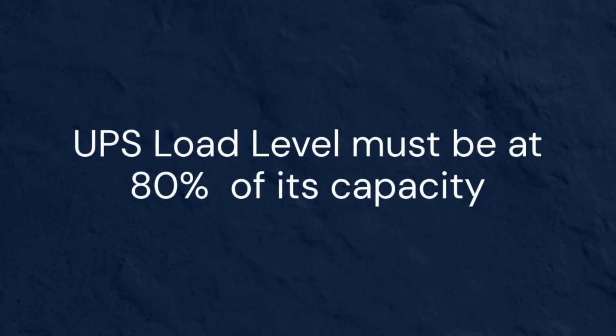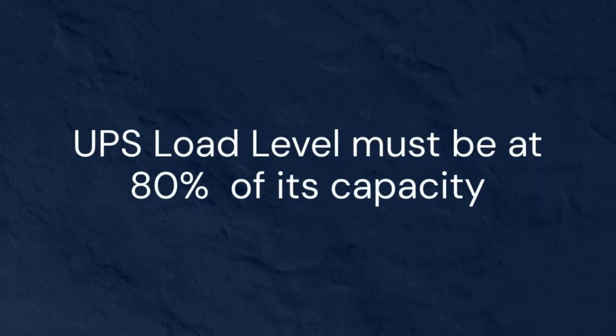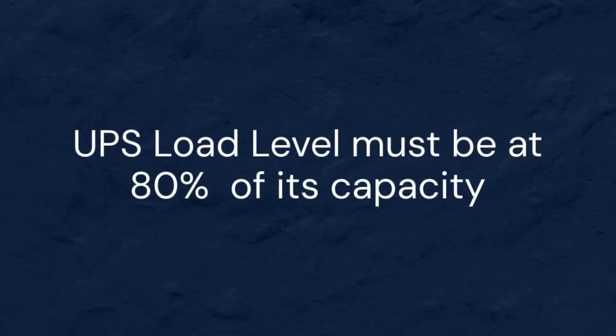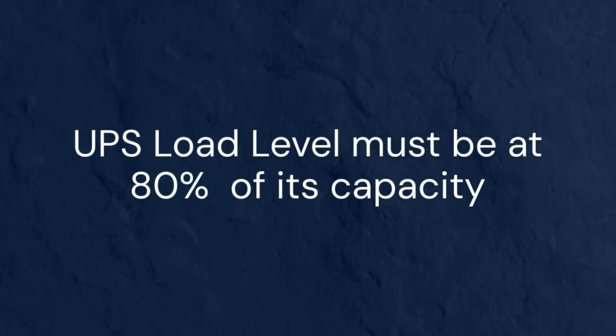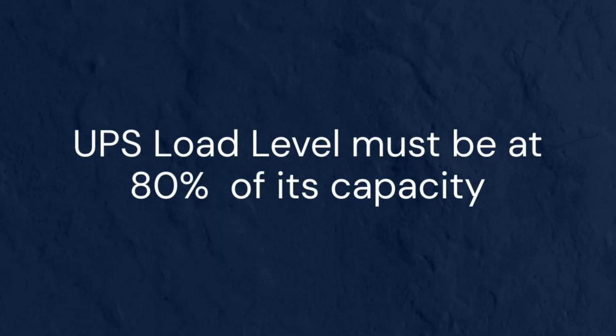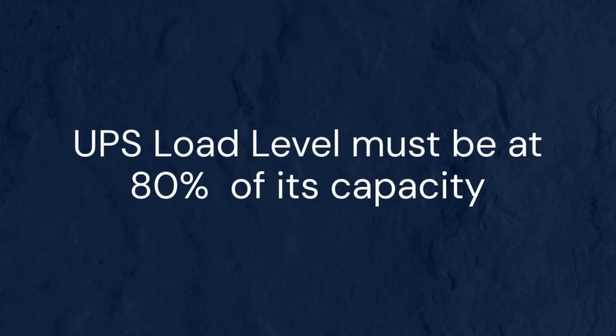E. Increasing the amount of load connected to a UPS will result in a shorter battery runtime. For longer battery life, it is recommended that the load must not exceed 80% of the UPS rated capacity.